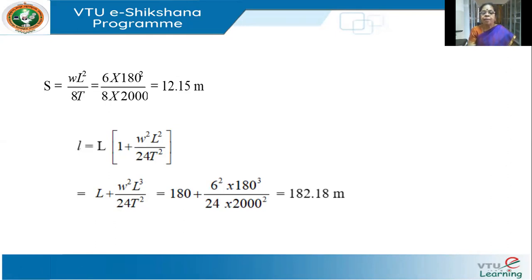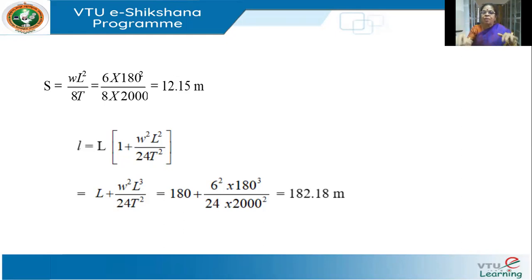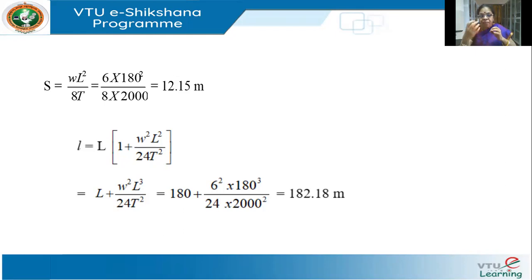From S = WL²/8T: SAG is proportional to the weight of the conductor — heavier conductors have more sag; proportional to the square of the span length — longer spans increase sag rapidly; and inversely proportional to tension — more tension means lesser sag, and a lower factor of safety means lesser sag.